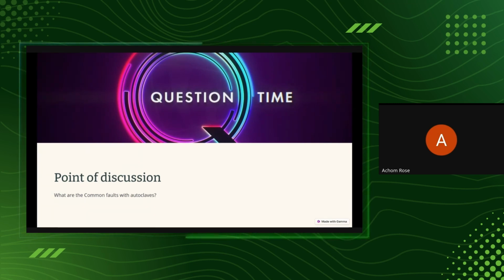However, for those where it is not practically possible, then you may have to do it manually, and you tell them to customize the settings. So instead of going to 121, please customize this setting and put 122, so that at 122 it is actually reading 121. The same thing with the timer. Tell them if it is not practically possible to do the internal adjustment, get an external timer and you time your measurements.